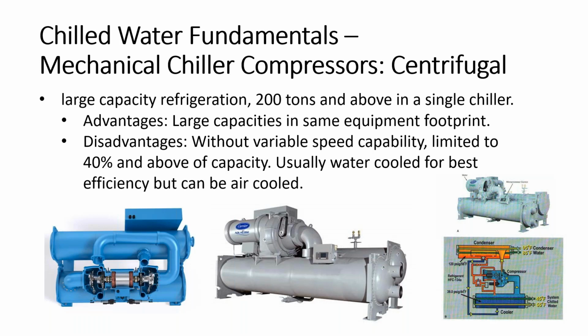They had a lot of trouble going in low capacity without variable speed. They were a constant speed machine. You controlled the refrigerant flow by inlet vanes. And if you got down to a certain point on low capacity, they started having trouble called surge. So you're basically starving the pump, the centrifugal machine, and it sounds like it's gasping for air, and you can actually hear it. I've been doing this so long, every time I hear that noise, I know exactly what it is, and I start to worry because it's either going to shut itself down or some damage may happen. You also get the same problem on the high side.